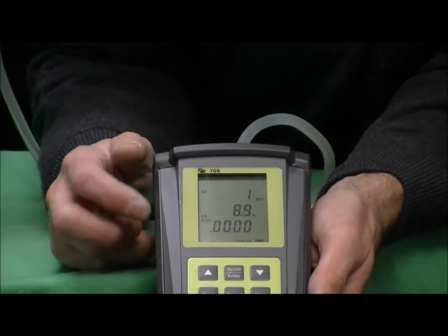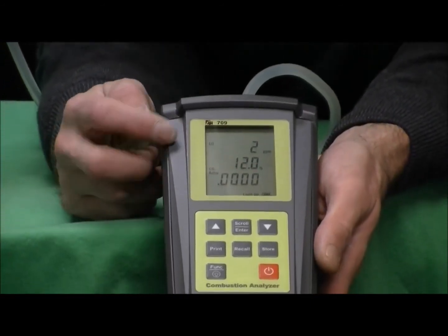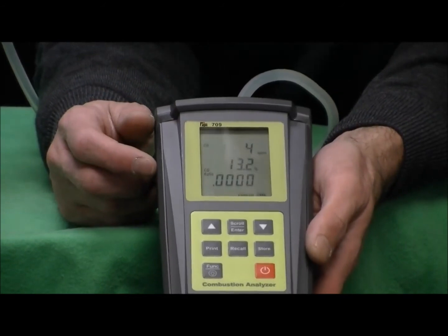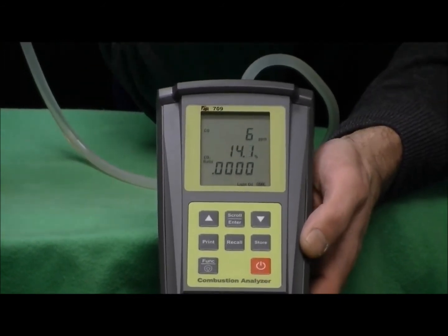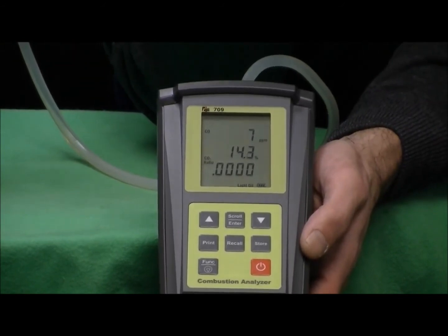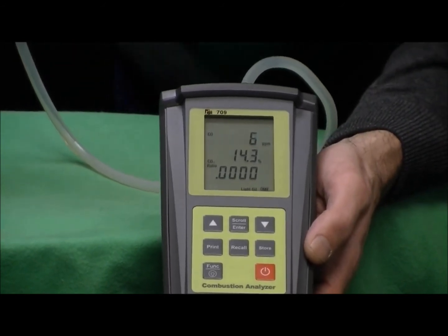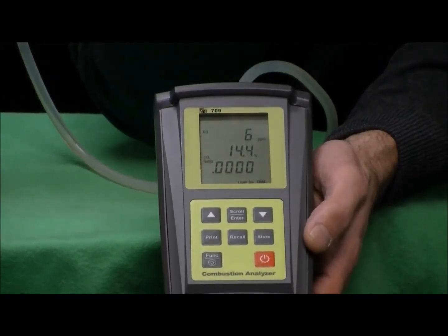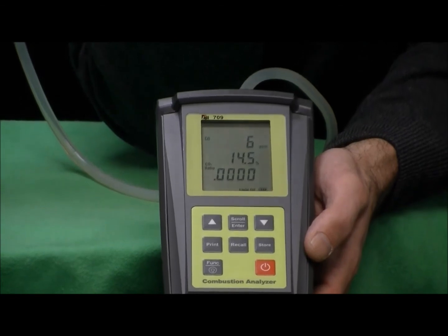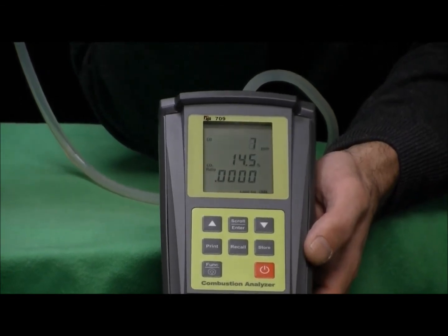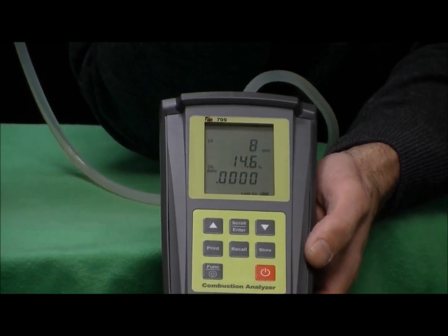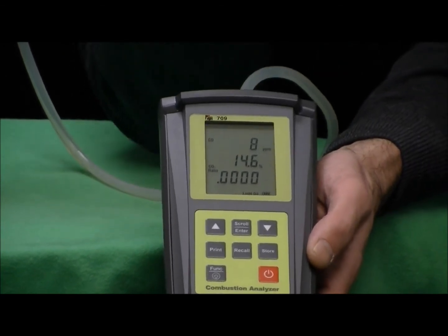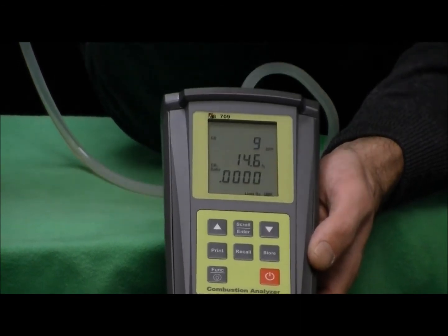You can see the first thing off the bat here, the CO2 is moving, CO is moving up. We're at 4, already 5, it's 6, 7. Now this canister can be plus or minus 10% in terms of its accuracy. And my analyzer now is showing 6, 7, 8 now parts per million. 9, bordering on 9. So it's very quick to react. And it's very accurate when we're talking about these low levels of carbon monoxide.